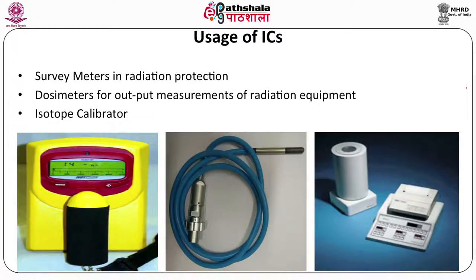Ion chambers are used as survey meters around radiation installations, to survey the amount of radiation for protection purposes. They are extensively used as dosimeters for radiation output measurements of equipment used in radiation therapy or radiology — for example, x-ray machines and radiotherapy machines. Similarly, ion chambers are also used as isotope calibrators, to determine the amount of radioactivity of a radioisotope being used in nuclear medicine or radiotherapy.